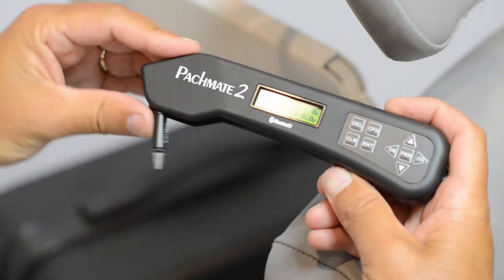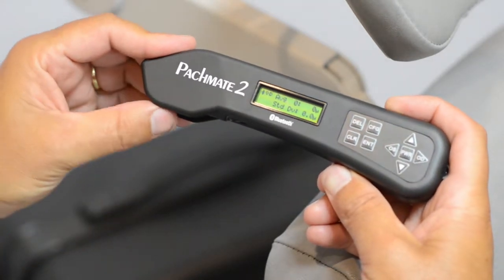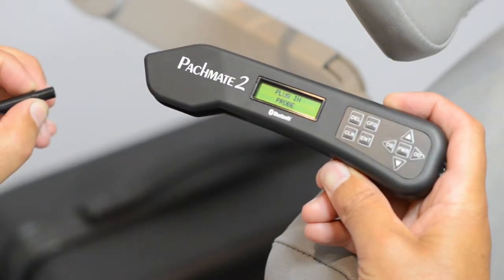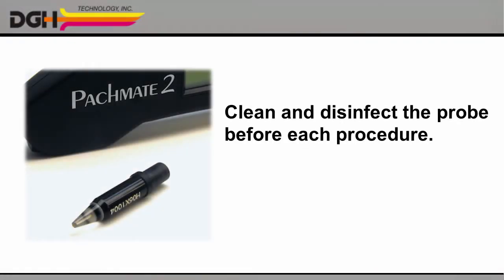Rotate the probe into the body of the device for protection during storage and transport, and pull it back out again the next time you need it. You can also detach the probe entirely for cleaning. It is important to clean and disinfect the probe before each pachymetry procedure to avoid cross-contamination and to reduce the risk of infection. Please see the user manual for details.